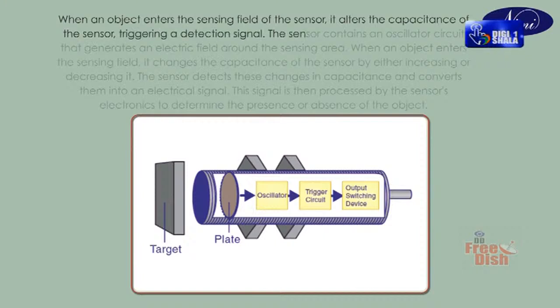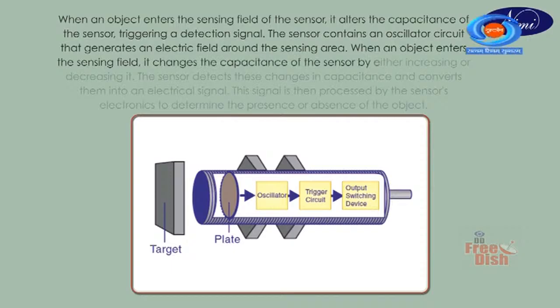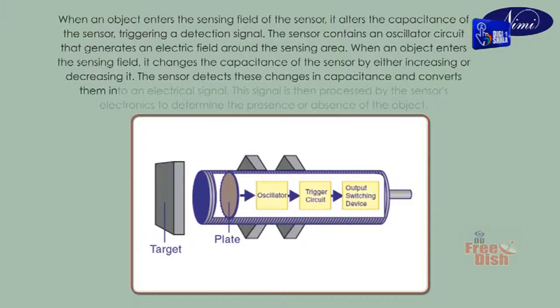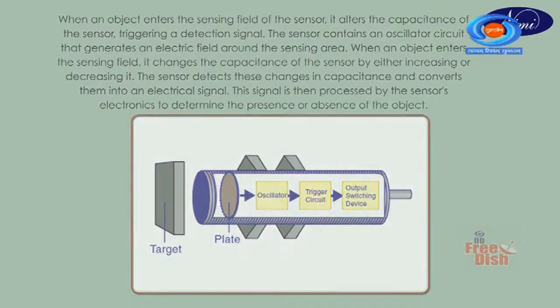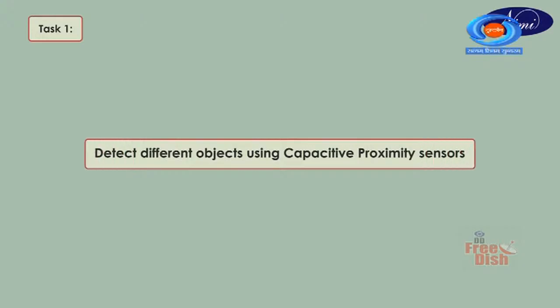The sensor contains an oscillator circuit that generates an electric field around the sensing area. When an object enters the sensing field, it changes the capacitance of the sensor by either increasing or decreasing it. The sensor detects these changes in capacitance and converts them into an electrical signal. This signal is then processed by the sensor's electronics to determine the presence or absence of the object. Task 1. Detect different objects using capacitive proximity sensors.